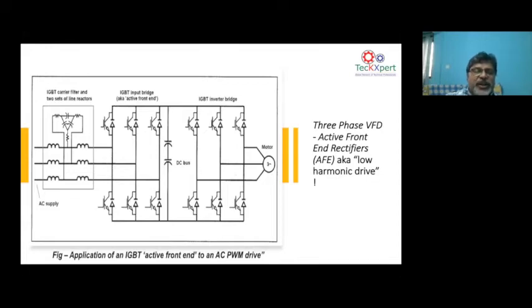The issue with active front-end drives: it's a good concept. Active front-end drives can reduce the harmonics, but at the same time, they increase the electromagnetic interference in the network, because an IGBT sitting at the front end of the drive produces high frequency currents in the network. So you will have issues with a lot of noise coming from active front-end drives when you put them in. You have to make sure that proper electromagnetic interference compliance is done before we put in such active front-end drives.